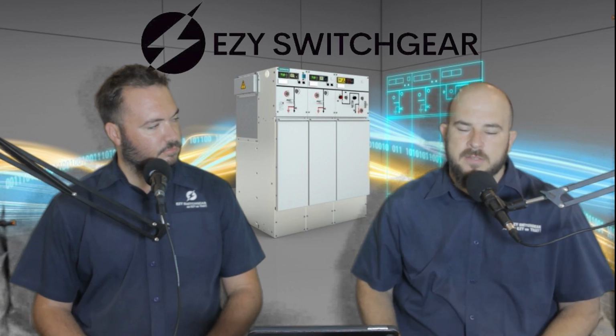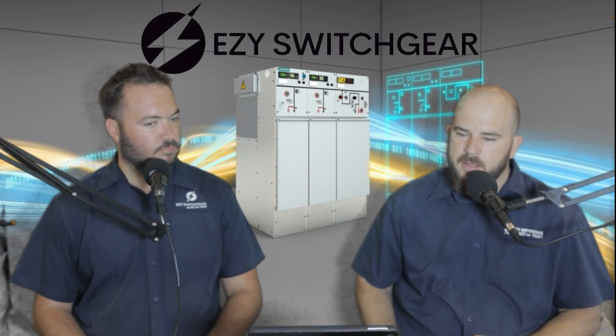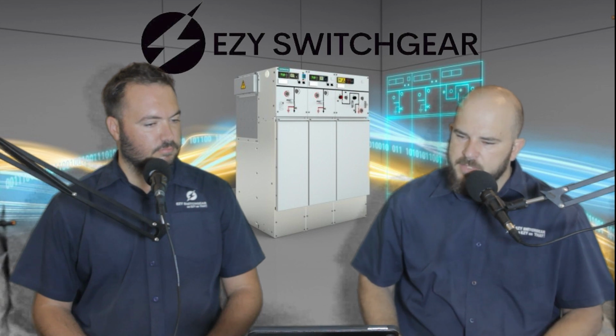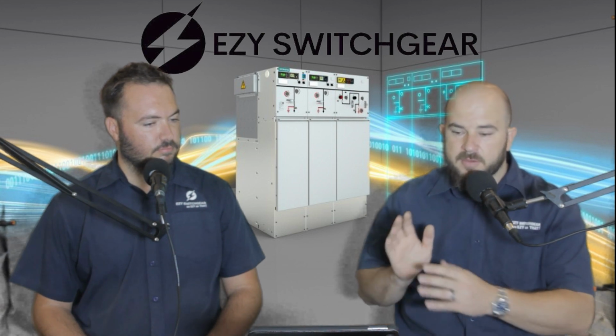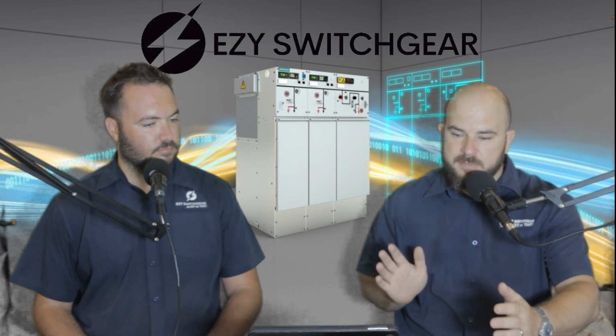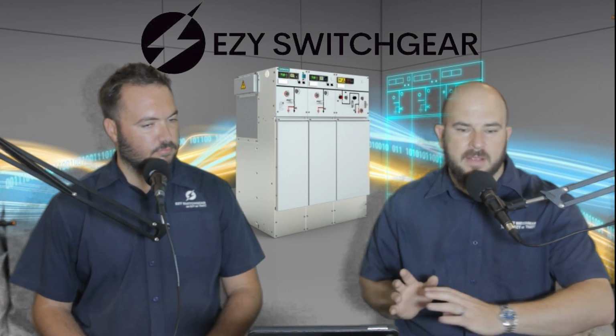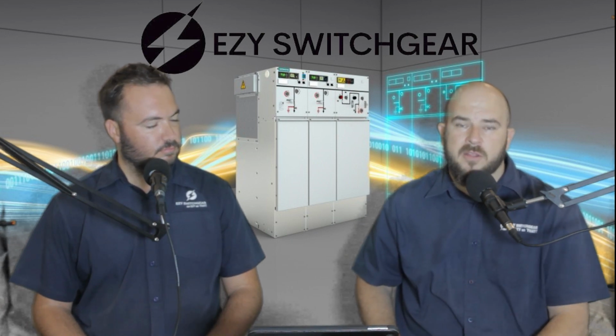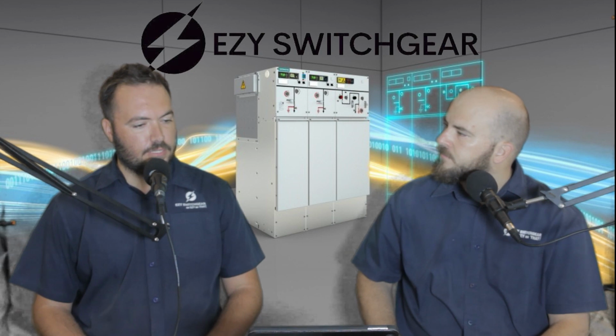That transformer steps down from 11,000 volts to 400 volts, which is then distributed in the network to your houses or to the factory where you operate. And so that switchgear fits into that space, protecting the transformer, the transmission lines, the cables and the network. Okay, great stuff.